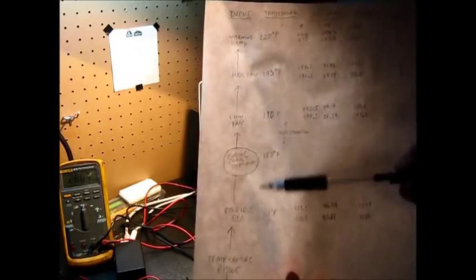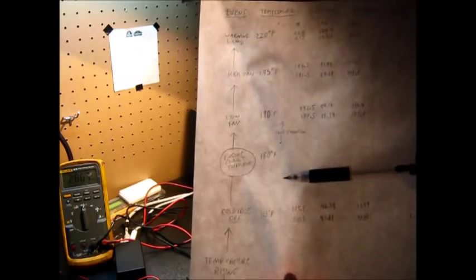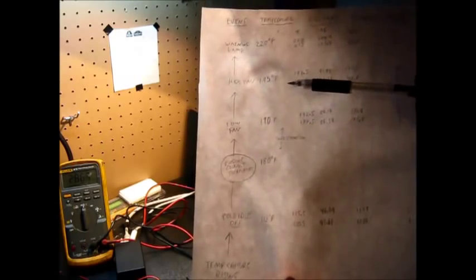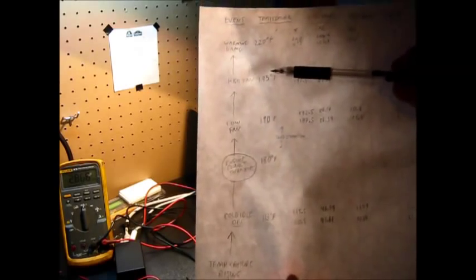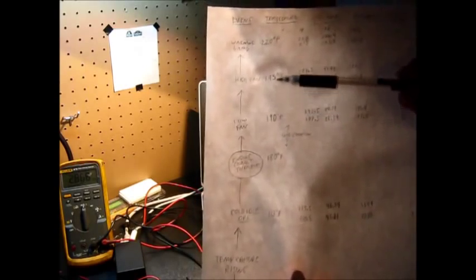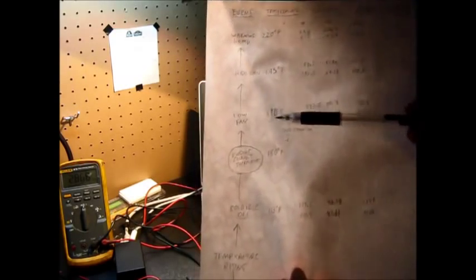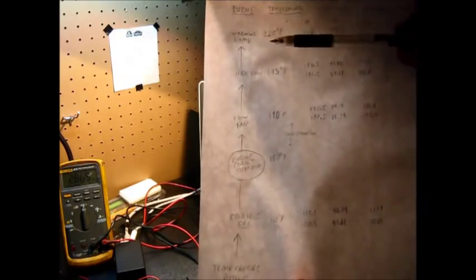These set points basically came from the service manual for the car. The fan temperatures, I'm changing them lower. They had that high speed coming on at like 240 Fahrenheit, which is way too hot. Each event needs to have a pair of set points, hysteresis pair, we call that.